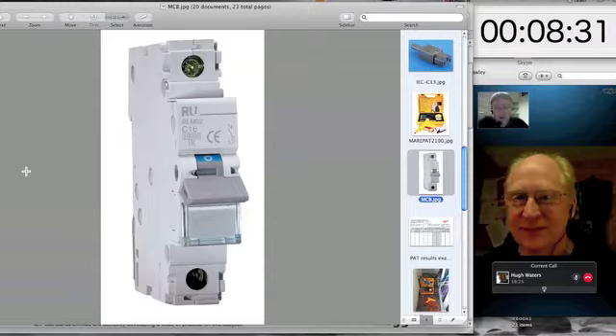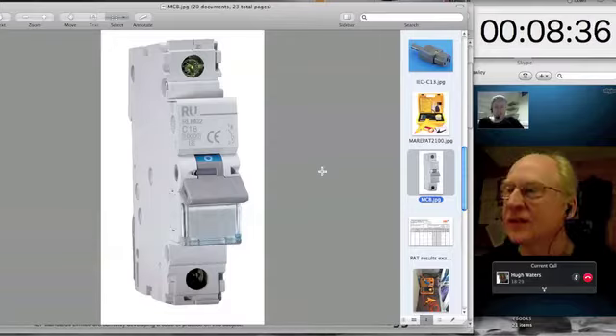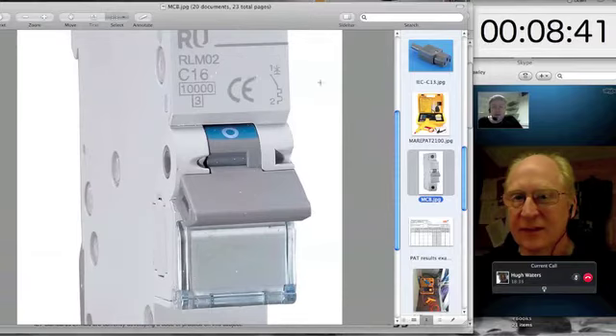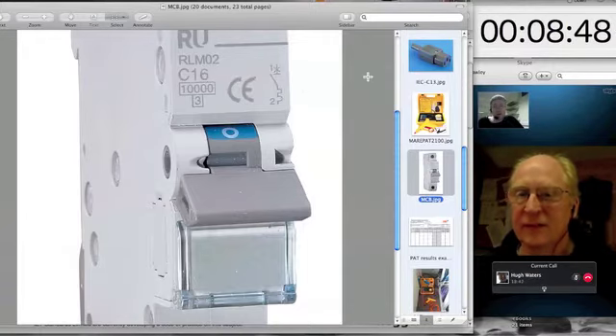You may well come across them in very old buildings, and they are replaced by what I have up on screen at the moment, which is what they call an MCB, a miniature circuit breaker. And let's just zoom in on this so it's a bit clearer. You can see it's marked. This one is a C16 MCB, so that will notionally pop at 16 amps. It's very typically rated for maybe a ring main circuit in a domestic premises where you might have a few plug points off it, or that is a very, very typical breaker that you might find feeding an equipment rack or an editing desk or something in our environment.